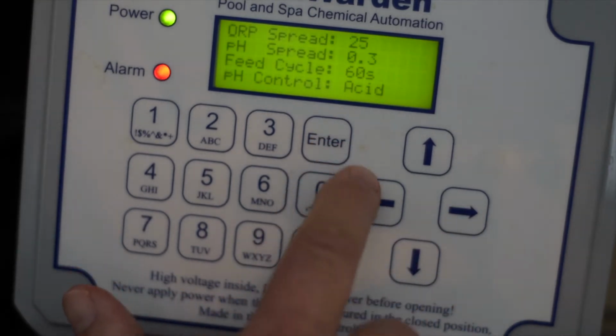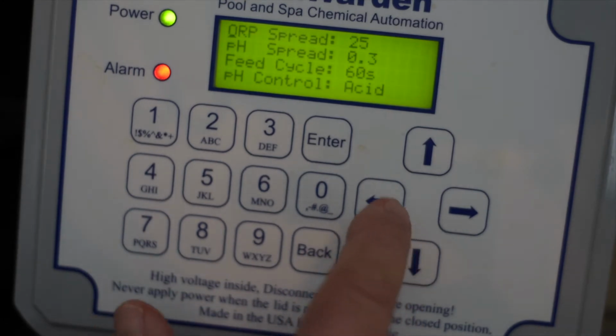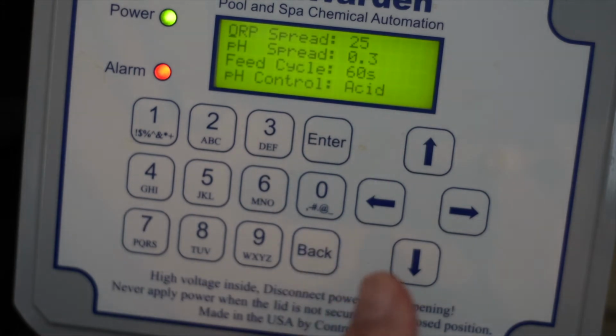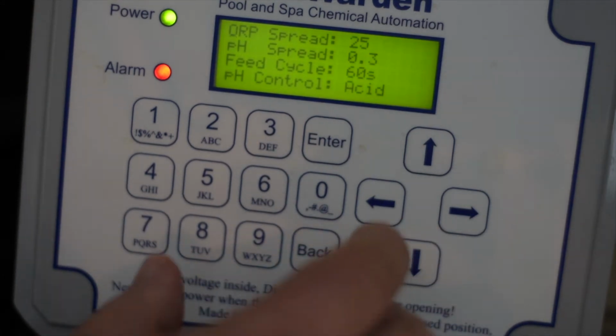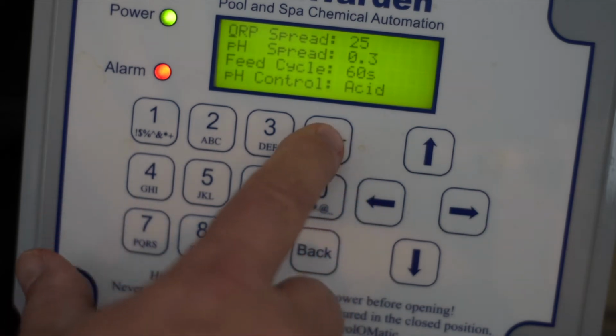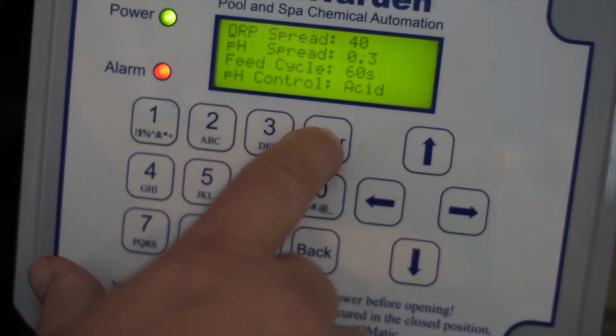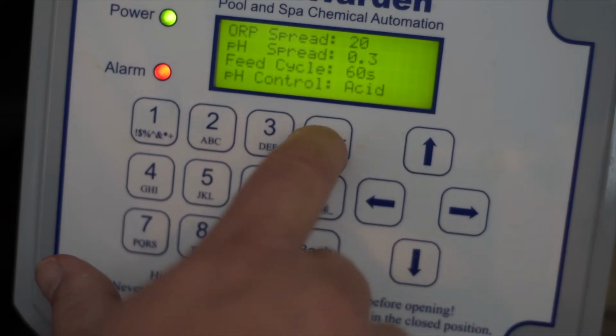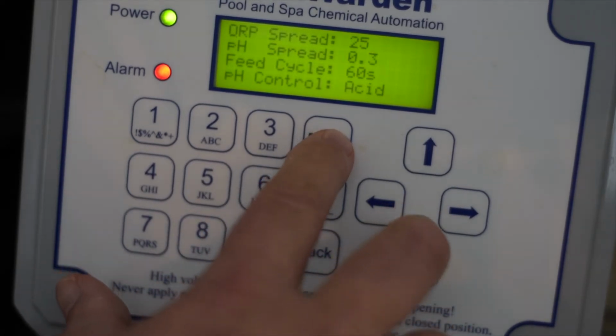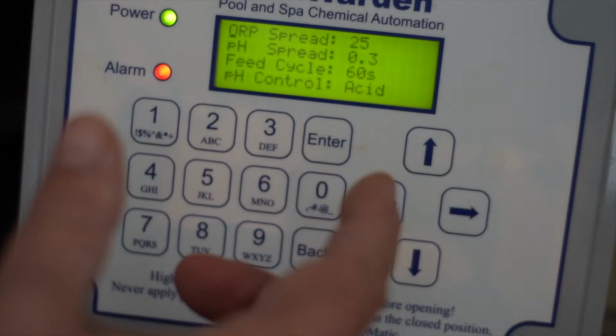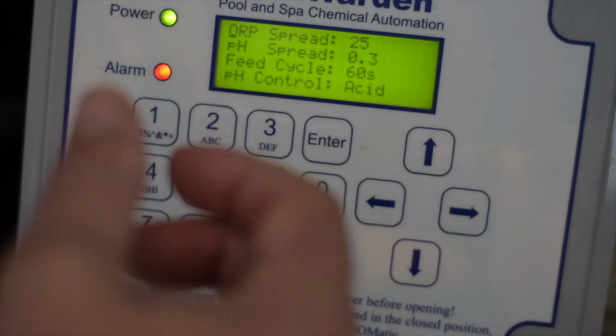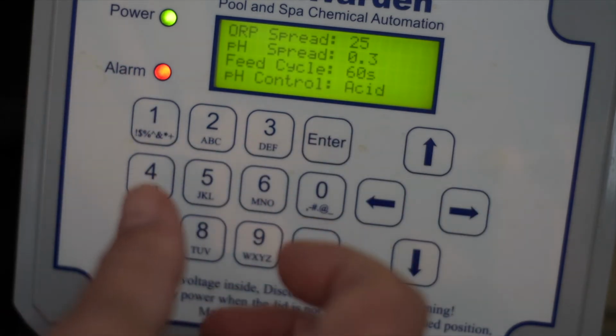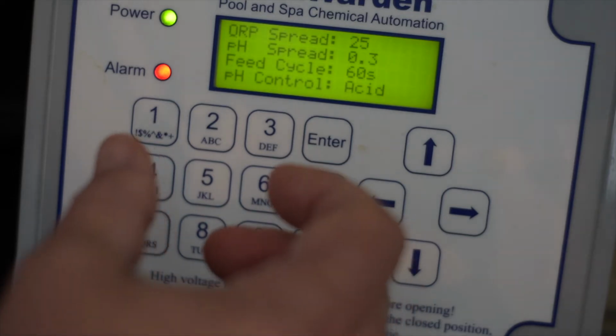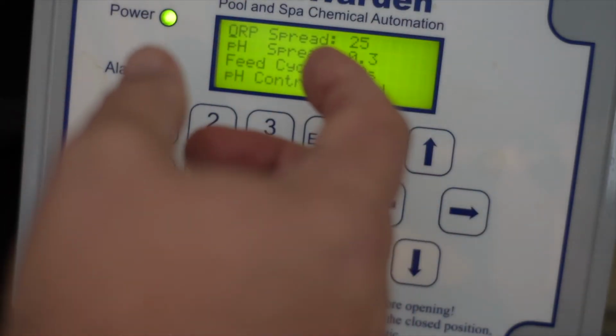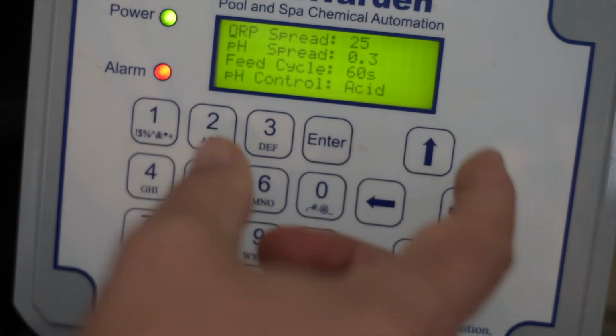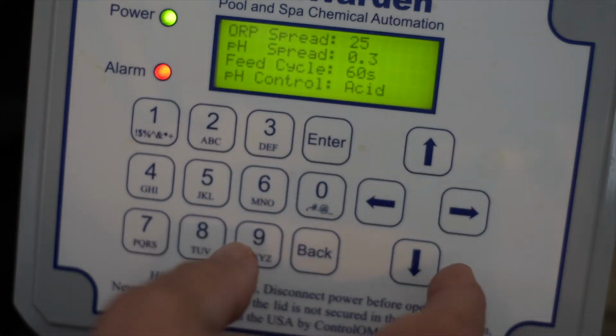go to options. Okay, ORP spread. Now this ORP and pH spread is both the proportional feeds, and this will help you to fine tune it. But we'll just start at 0, then it goes 10, 15, 20, 25. So that's a good place to start. If your ORP goes below 25 millivolts under your set point, it will be on continuously until it gets under that 25 millivolt spread, and then it will go into proportional.